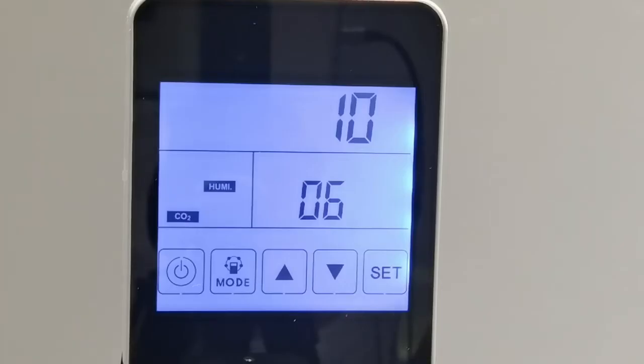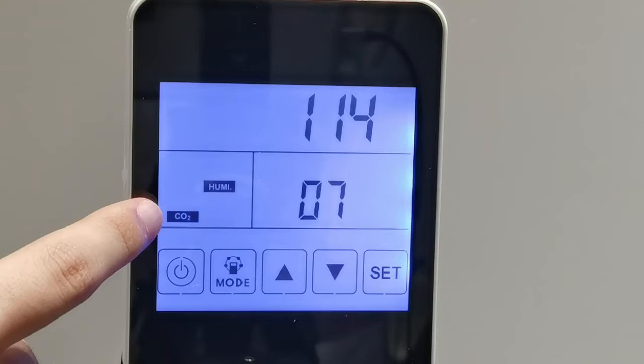Now let's press the set button one more time to move into parameter 07. Okay, 07 refers to the CO2 concentration control. After connecting the CO2 sensor, the CO2 symbol will display on the panel.